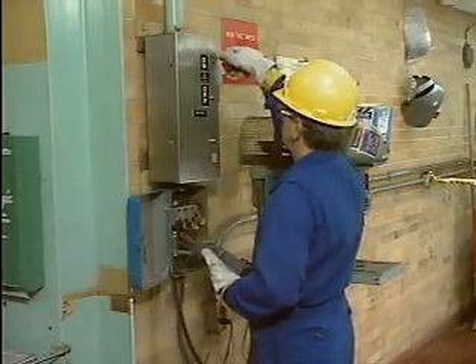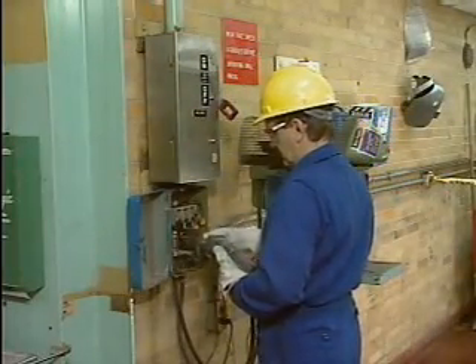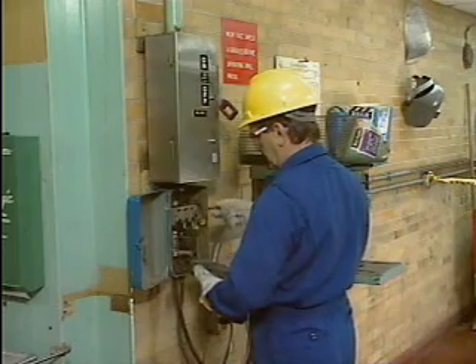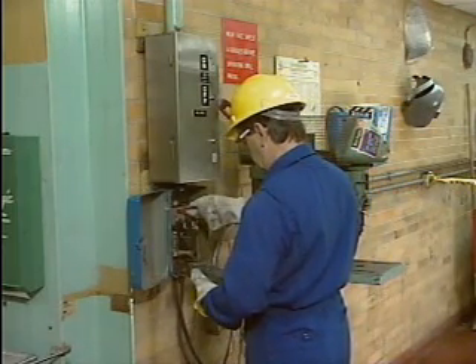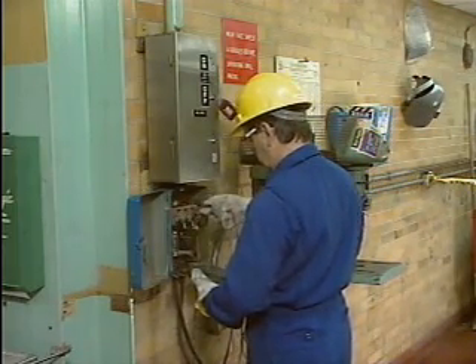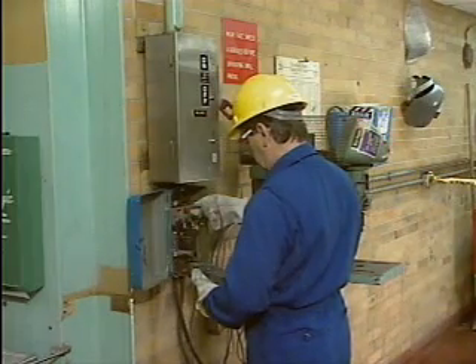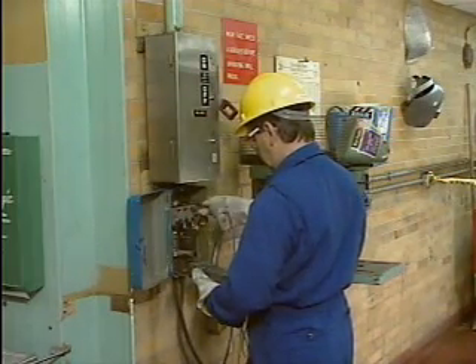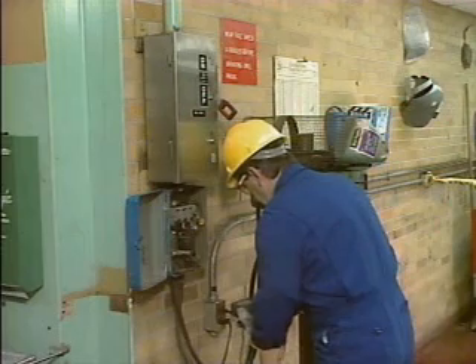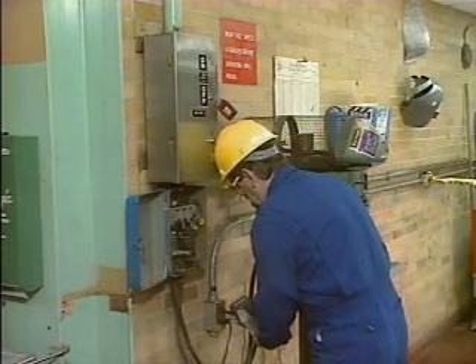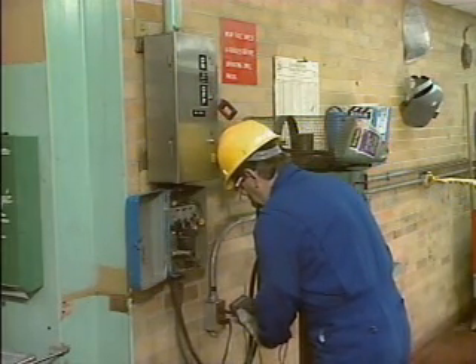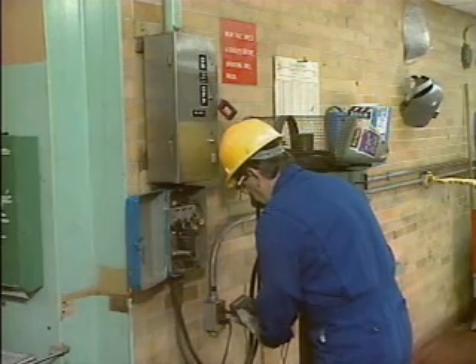Because it's safer to work on a circuit that is not energized, the electrician turns off the power switch. To be sure that the circuit is not energized, the electrician measures the voltage at the point where it enters the control cabinet and reads 0 volts at each phase. Then he verifies that the voltmeter is still operating properly. This confirms that the voltage to the circuit has been shut off.